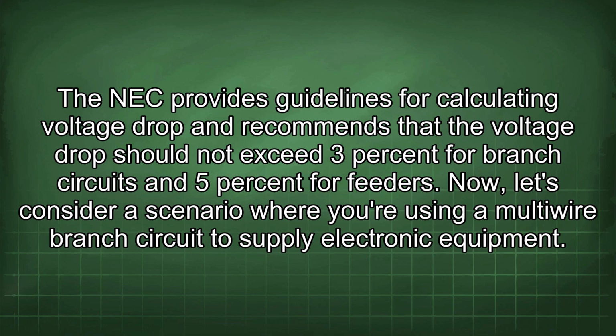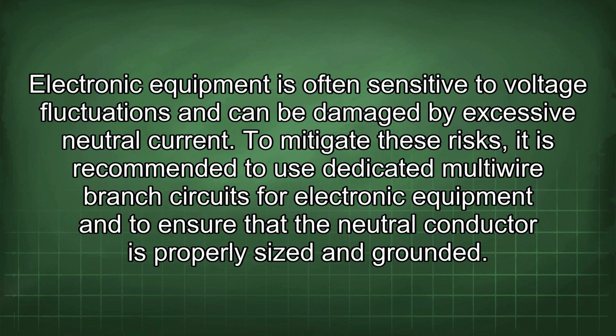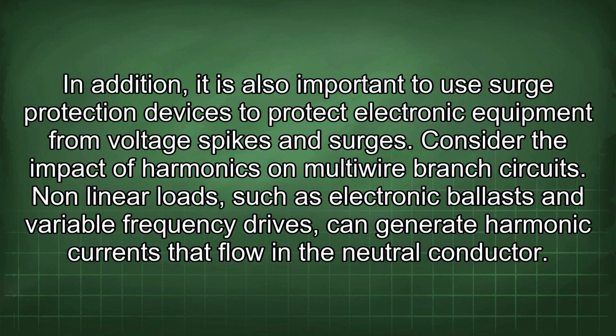Now let's consider a scenario where you're using a multi-wire branch circuit to supply electronic equipment. Electronic equipment is often sensitive to voltage fluctuations and can be damaged by excessive neutral current. To mitigate these risks, it is recommended to use dedicated multi-wire branch circuits for electronic equipment and to ensure that the neutral conductor is properly sized and grounded. In addition, it is also important to use surge protection devices to protect electronic equipment from voltage spikes and surges.